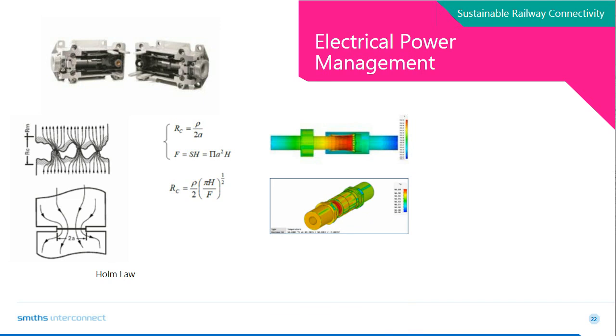The second very influential parameter is the surface. The bigger the surface is, the lower the electrical resistance is. For that reason, it's important to use an elastic contact offering a large surface of contact. If you combine a large surface of contact with good conductive plating, you can significantly decrease electrical resistance and therefore temperature rise due to Joule effect.